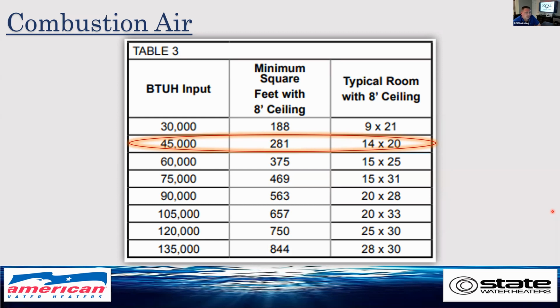And I also need to look into whether there are other gas appliances, such as a furnace, using the same combustion air that must be accounted for as well. So if you had a 90+ furnace in that same room, that 45 and that 90 would give you 135 BTUs that you need for combustion air, and you need a room size of 28 by 30.